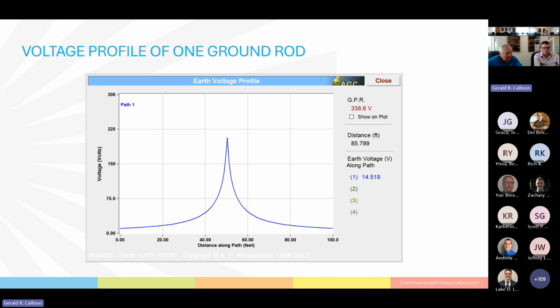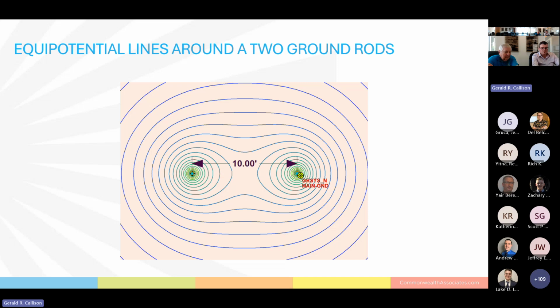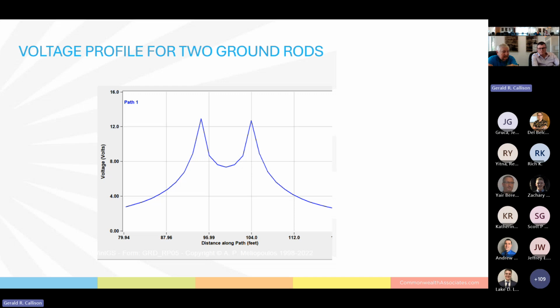So this is what the voltage profile looks like for one ground rod. The potential drops off fairly rapidly at the edge of the ground rod, and that will extend out until the voltage essentially goes to zero at remote Earth. What happens if you put two ground rods relatively close together? You energize both of the ground rods, and the equal potential lines are no longer nice concentric circles. On the outside they look like ovals, and inside, kind of like a figure eight. When you look at the potential profile, the voltage does not drop off in between the rods like it does on the edges of the two ground rods.